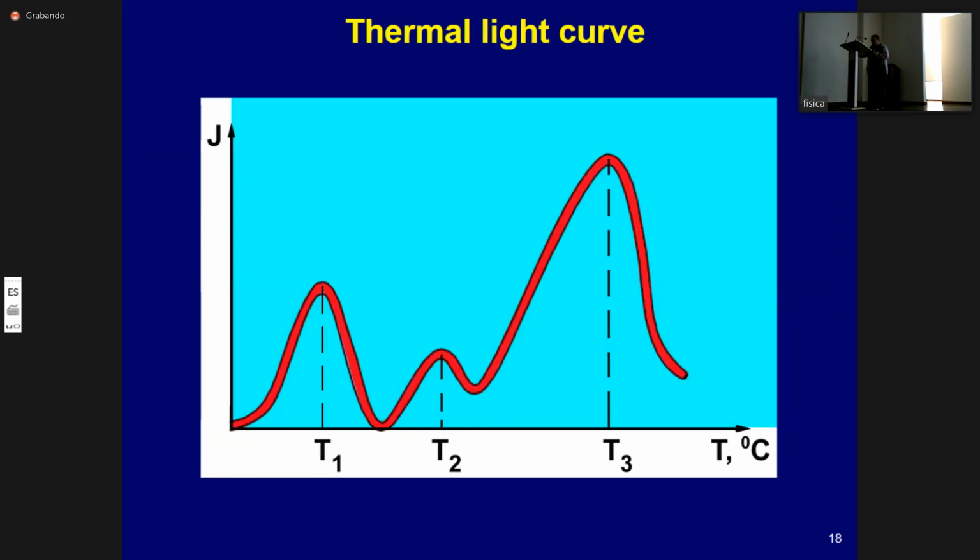The glow of thermoluminescence serves as a measure of the dose of ionizing radiation absorbed in the detector. The measurement procedure for the dose using a TLD is based on the irradiated detector being heated at a given constant rate. And during heating, the dependence of the luminescence intensity J on the phosphor temperature T is measured.